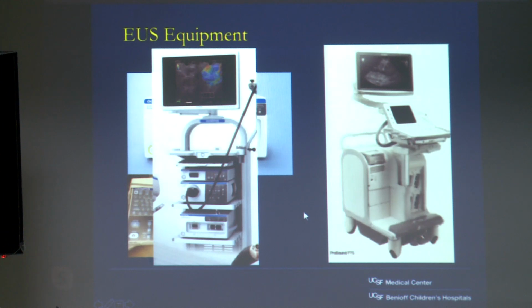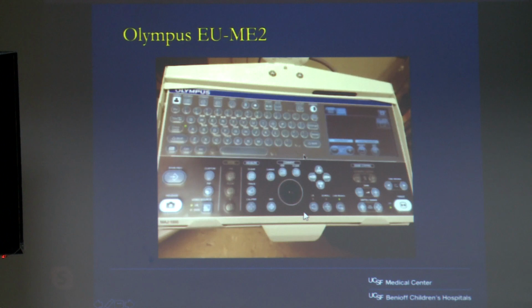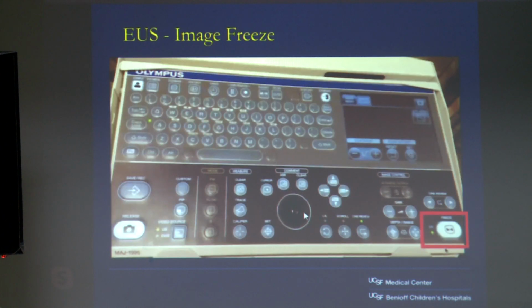So the basic keyboard is one you have to be familiar with. Of course, you have the alphabets and the numbers, and then you have these different buttons and the tracker ball, as well as a touch screen in the right upper corner for the different features. The first one to be aware of is the freeze button, which basically allows the ultrasound signal to be transmitted or stopped. So when the scope's attached and you're not seeing a signal, the first thing to do is to check: is the freeze button on? Maybe that's why you're not getting a signal. And it's best to always check that outside the patient, in a little jar of water, to make sure that you have a signal and you can see that your ultrasound scope is functional.